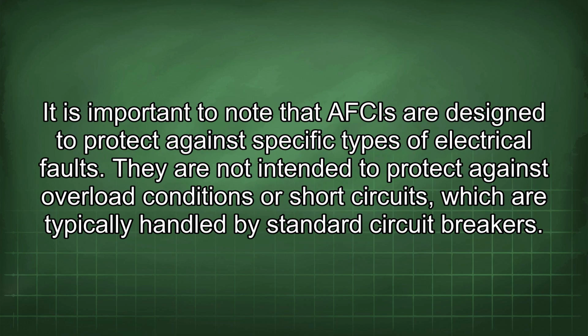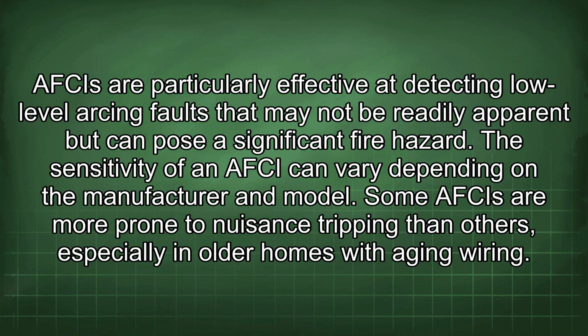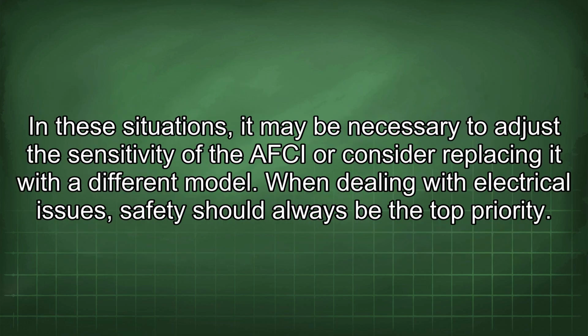It is important to note that AFCIs are designed to protect against specific types of electrical faults. They are not intended to protect against overload conditions or short circuits, which are typically handled by standard circuit breakers. AFCIs are particularly effective at detecting low-level arcing faults that may not be readily apparent but can pose a significant fire hazard. The sensitivity of an AFCI can vary depending on the manufacturer and model. Some AFCIs are more prone to nuisance tripping than others, especially in older homes with aging wiring. In these situations, it may be necessary to adjust the sensitivity of the AFCI or consider replacing it with a different model. When dealing with electrical issues, safety should always be the top priority.